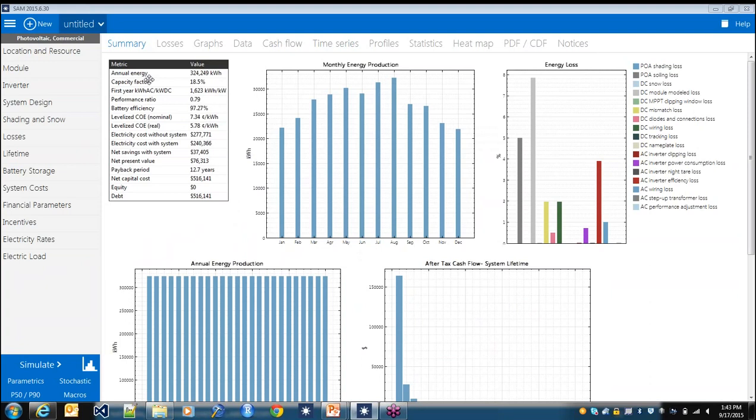And so, as I mentioned, it's not ideal for peak shaving because you have to really dig into your load profile and then start tailoring the controller very specifically depending on the month and the hour. But you can start to chip away at some of the demand charge.